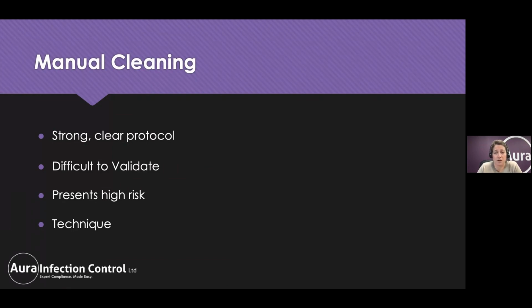If we consider manual cleaning, first of all, manual cleaning governed by an appropriate protocol is acceptable within EQR, Essential Quality Requirements Framework. And in principle, manual cleaning is the simplest method to set up, but it is difficult to validate because it's difficult to ensure that what's being carried out is the same on every occasion. And compared to other cleaning methods, manual cleaning presents a greater risk of inoculation injury to staff. That being said, all practices need to have a manual cleaning protocol and backup in case other methods are not available or not appropriate. So your manual cleaning policy and procedure should be nice and detailed.